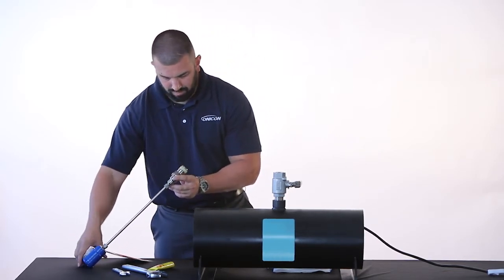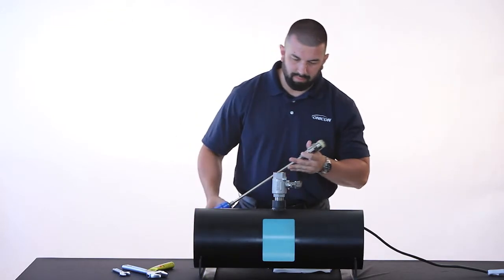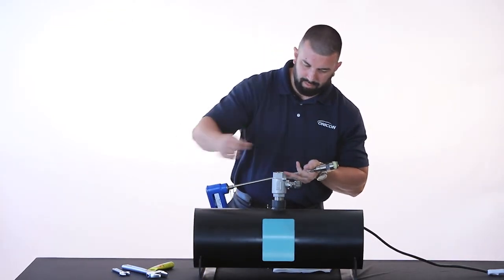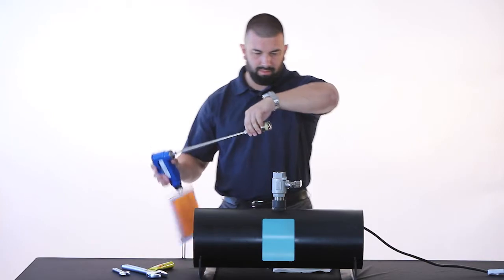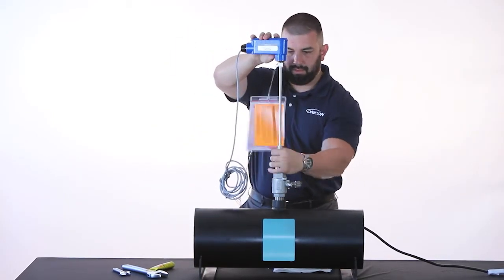Inspect the inside of the ball valve to make sure the threads are clean. Then with the sensing assembly fully retracted, position the flow meter in line with the ball valve opening and carefully thread the hot tap adapter into the ball valve.